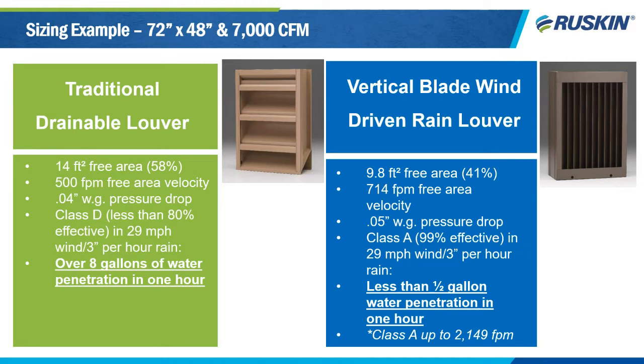On the right is a 6-inch deep vertical wind-driven rain louver, and note that it has 25% less square footage of free area, which leads to a higher intake velocity. But also note that the pressure drop is almost identical, meaning it's essentially no harder to move the air through it than the standard louver, even though the wind-driven rain louver has less free area. And the wind-driven rain louver is 99% efficient, allowing less than half a gallon of water carryover through it. Additionally, this wind-driven rain louver provides Class A resistance up to 2,149 feet per minute free area velocity, meaning you will need very little, if any, oversizing of the louver to take it from standard air intake to maximum air.